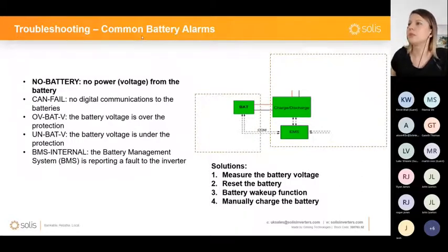I'm going to tell you a bit about the most common battery alarms. There's no battery. The no battery one, that's the most common. That happens even if the battery is connected but was not turned on. It will give a no battery alarm. CAN communication failure, CAN fail. It's an alarm related to the communication between the battery and the inverter. You can have the no battery and CAN fail at the same time, as they can happen at the same time when the battery is completely turned off and not communicating.